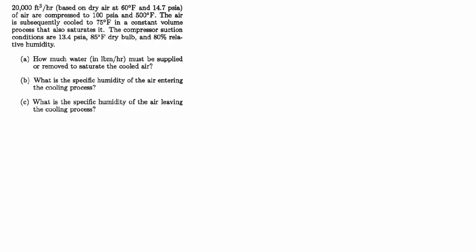20,000 cubic feet per hour, based on dry air at 60 degrees and 14.7 psia of air, are compressed to 100 psia and 500 degrees. The air is subsequently cooled to 75 degrees in a constant volume process that also saturates it. The compressor suction conditions are 13.4 psia, 85 degrees dry bulb, and 80% relative humidity. They want to know: (a) how much water in pounds per hour must be supplied or removed to saturate the cooled air, (b) what is the specific humidity of the air entering the cooling process, and (c) what is the specific humidity of the air leaving the cooling process.